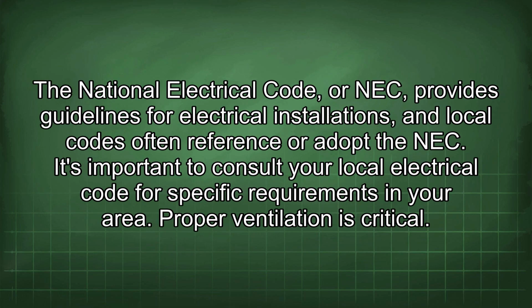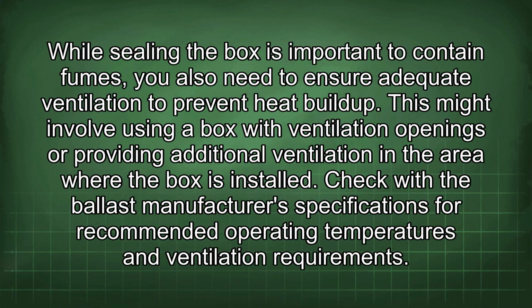The National Electrical Code, or NEC, provides guidelines for electrical installations, and local codes often reference or adopt the NEC. It's important to consult your local electrical code for specific requirements in your area. Proper ventilation is critical. While sealing the box is important to contain fumes, you also need to ensure adequate ventilation to prevent heat buildup. This might involve using a box with ventilation openings or providing additional ventilation in the area where the box is installed. Check with the ballast manufacturer's specifications for recommended operating temperatures and ventilation requirements.